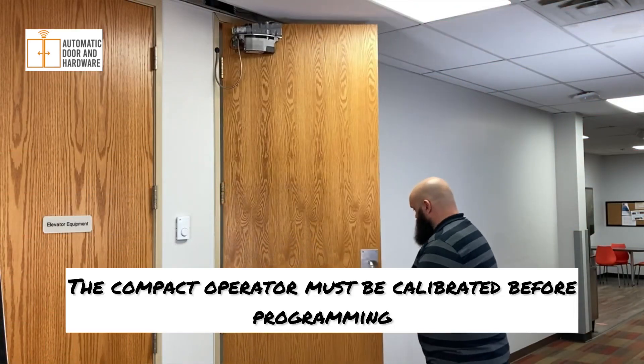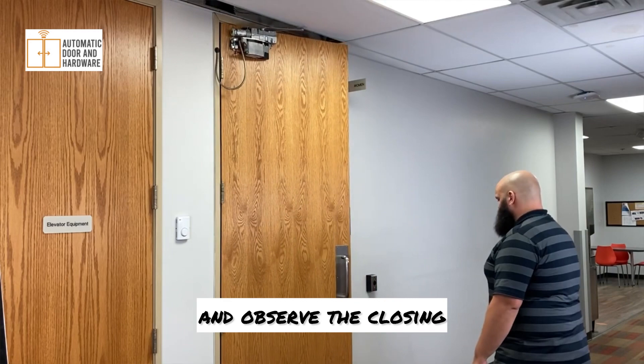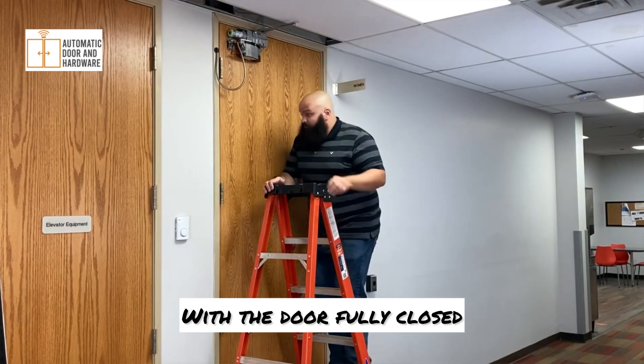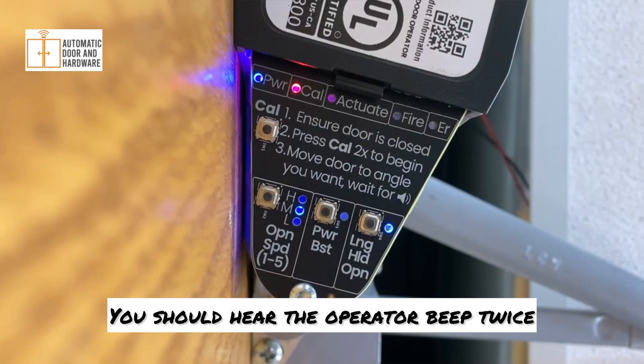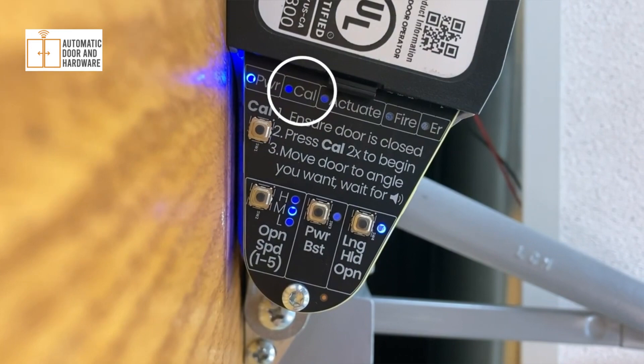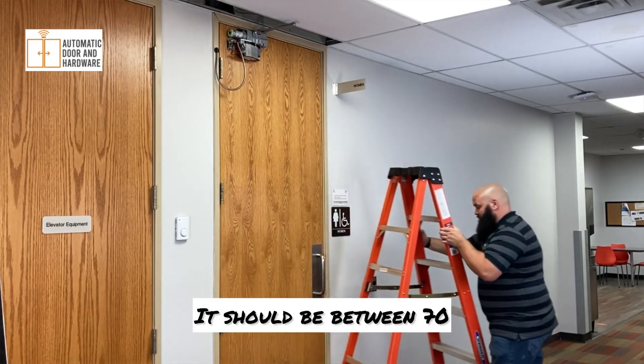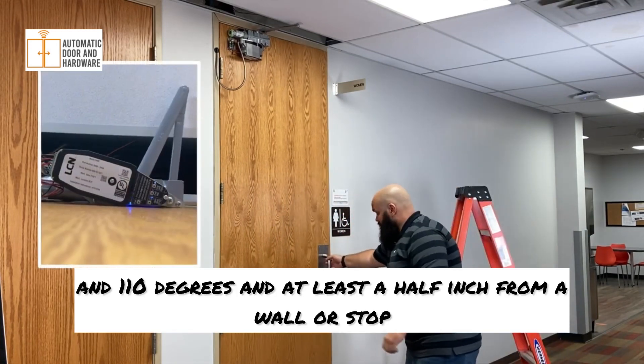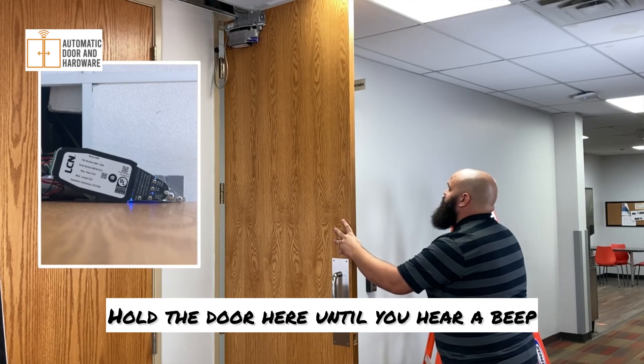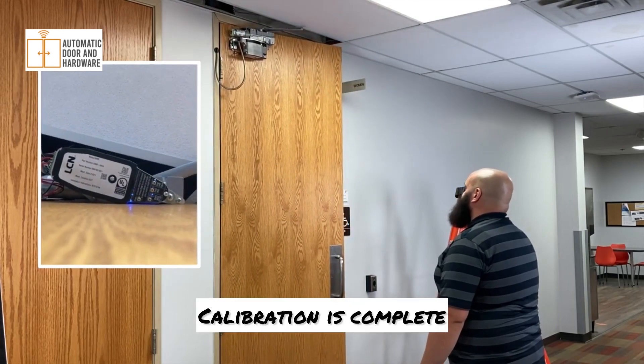The compact operator must be calibrated before programming. First, open the door, release, and observe the closing. Make adjustments to the closer as necessary. With the door fully closed, press the Cal button twice. You should hear the operator beep twice and see the Cal light blinking blue. Open the door to your preferred fully open position — it should be between 70 and 110 degrees and at least a half inch from a wall or stop. Hold the door here until you hear a beep. The Cal light should now be a solid blue. Calibration is complete.